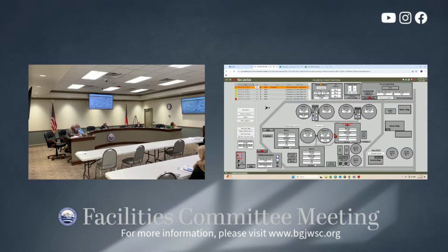It says on each of these clarifiers, you'll have a RAS flow leaving the clarifier. Now we have a flow meter that needs to be replaced. So these 2 are reading 0, even though those are online. And you'll see 3 of them, or 2 of them have, it says sludge blanket. We're testing some real-time sludge blanket monitors, and we're having some issues getting them to read correctly. So those numbers are complete garbage. We don't have a negative sludge blanket. That's impossible to happen. Because that means you would have, below the concrete.